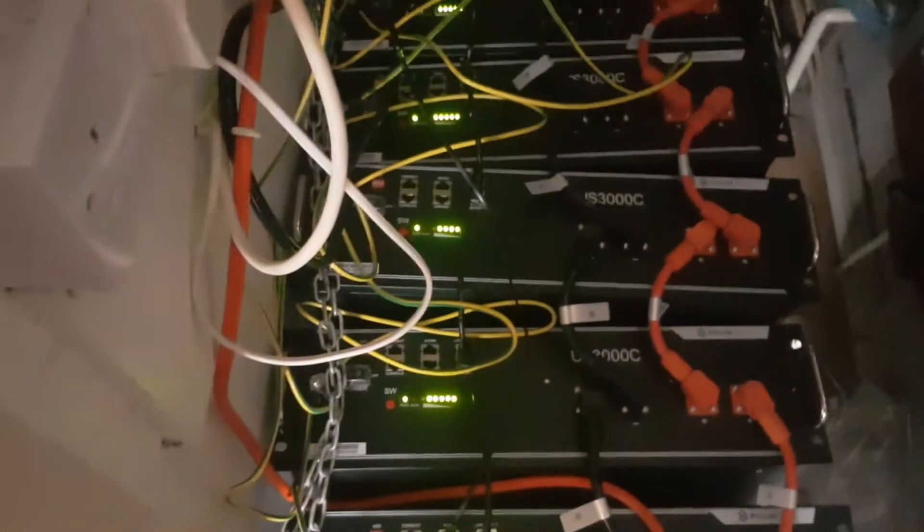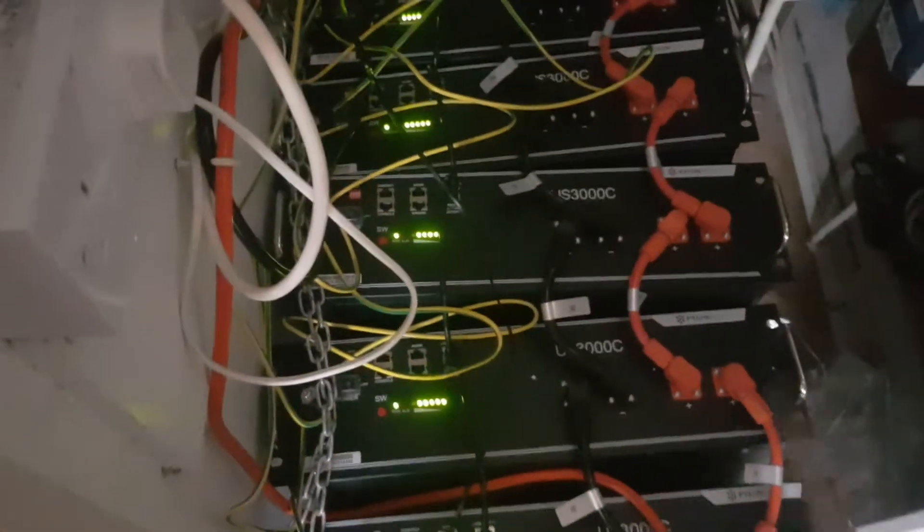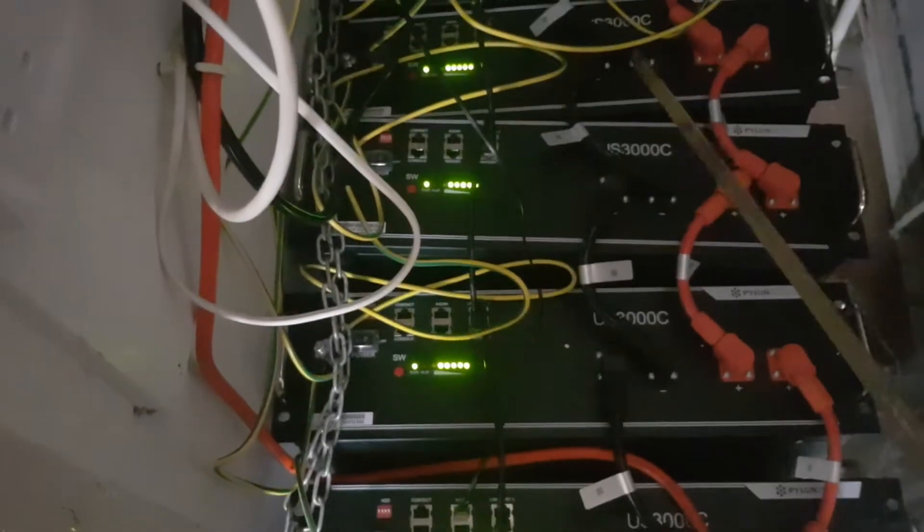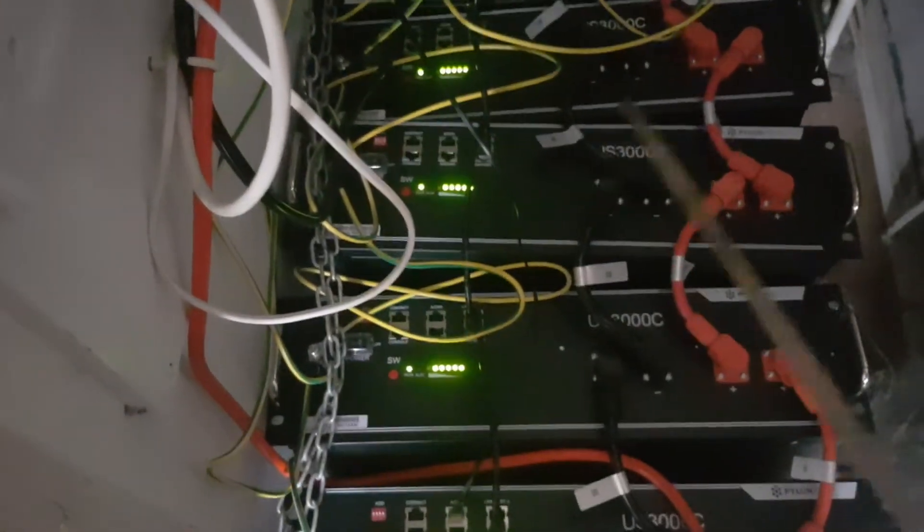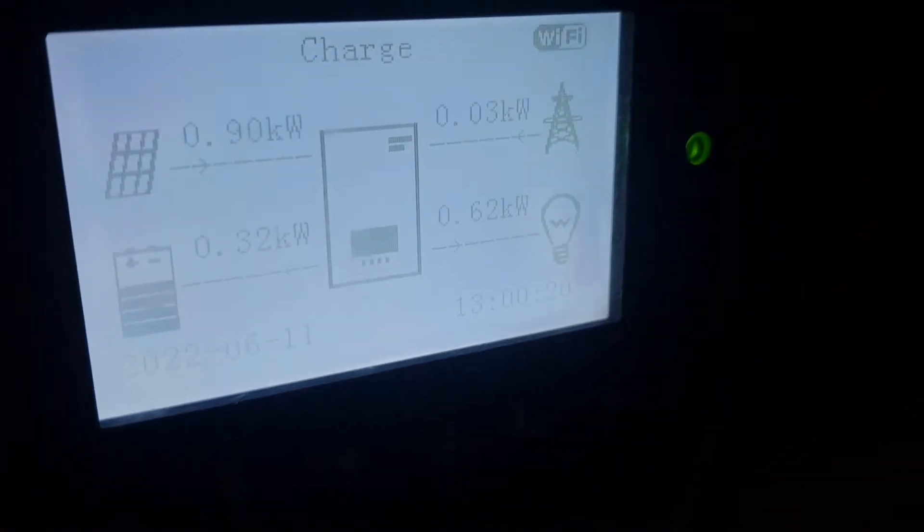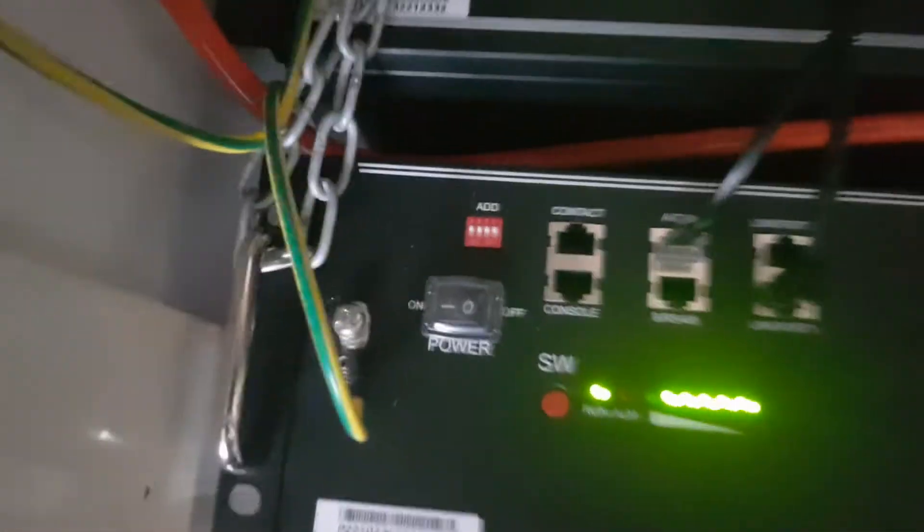When you get a fault on these, one of the cells within each battery may fail, and that will cause one of these batteries to fail. Your inverter itself would actually flag the fault up, and the alarm light will come on. You can see the alarm light just underneath the green light there, and so then you'll notice something wrong in one of your batteries.